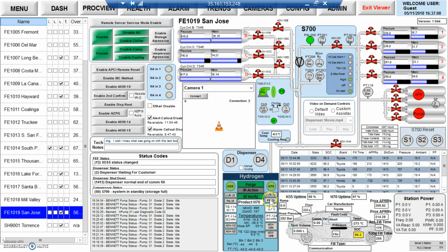Lastly, I want to talk about some of these numbers that are in here. This is the E122. This is the thermocouple that's at the bottom left of our dispenser, right? The inlet temperature. This is the hose set point. This is basically what the temperature of the hose will be. It should always be set at -33. Eventually, we will dynamically change that based on the ambient temperature.